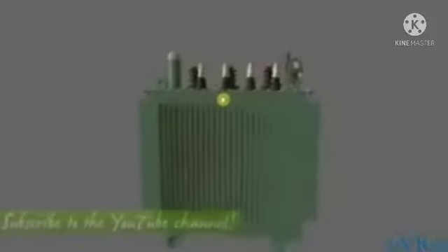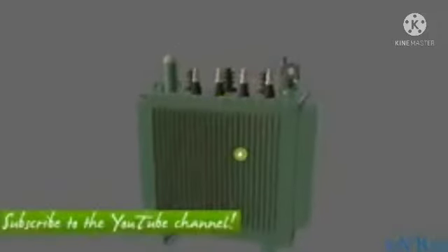So essentially, the hermetic type transformer is a dry type transformer, but with a box around it, or a casing, that is full with an insulating liquid. Now this insulating liquid is typically mineral oil. About 95% of the time it's going to be mineral oil. And the whole thing sits in a bath of mineral oil. The reason it's called hermetic is because it is totally isolated from the atmosphere, or from the external environment.